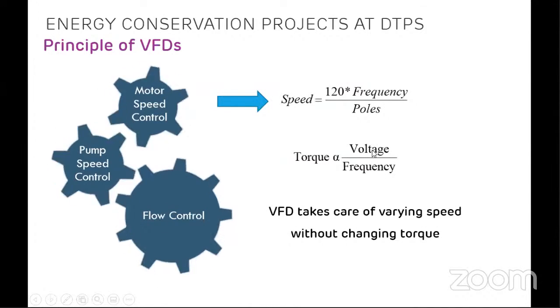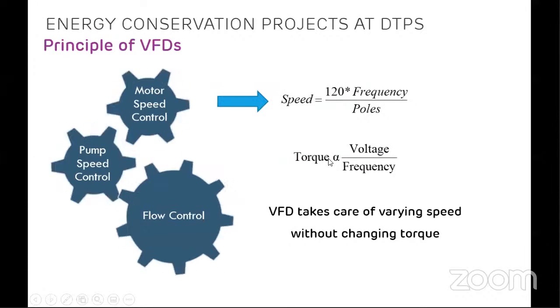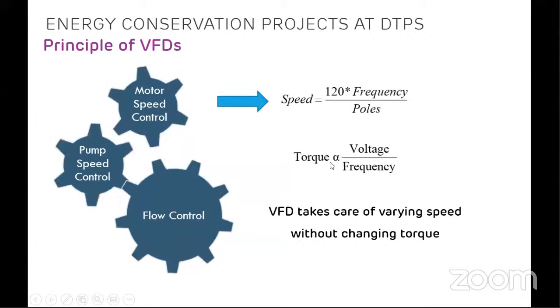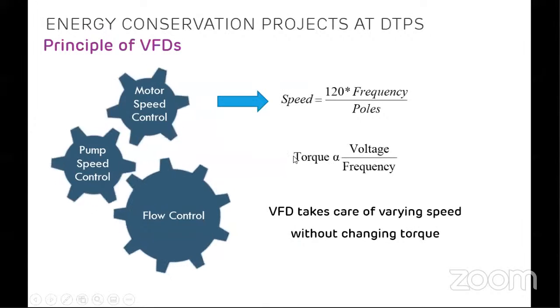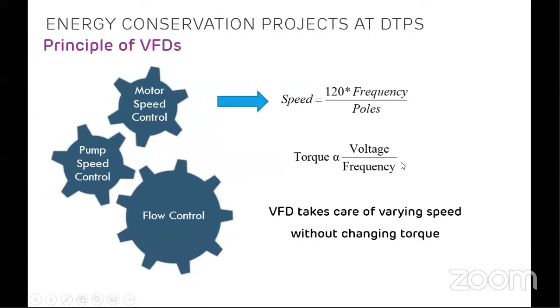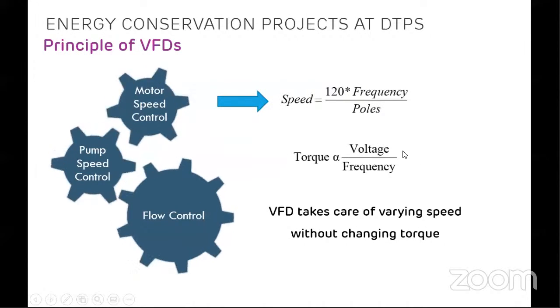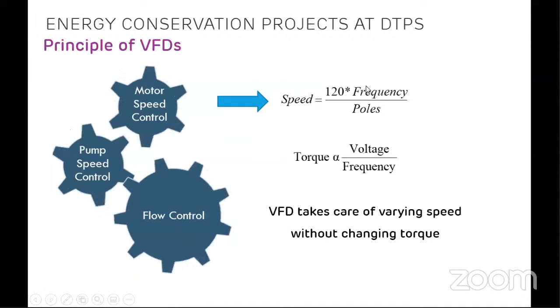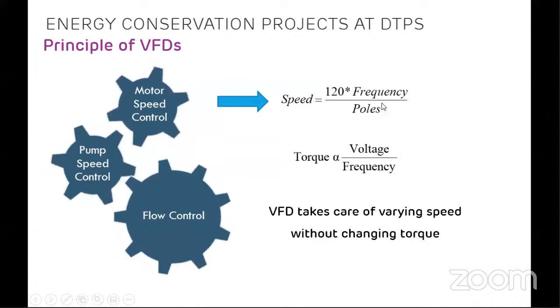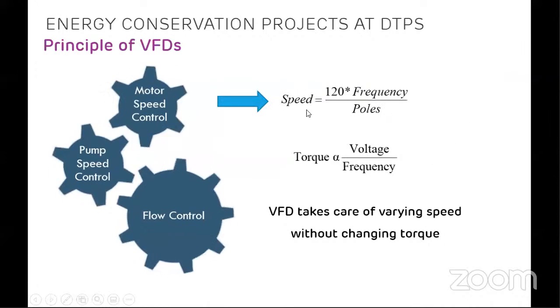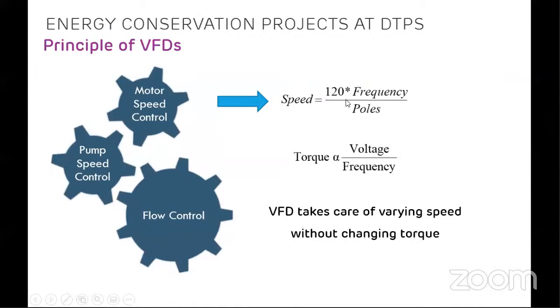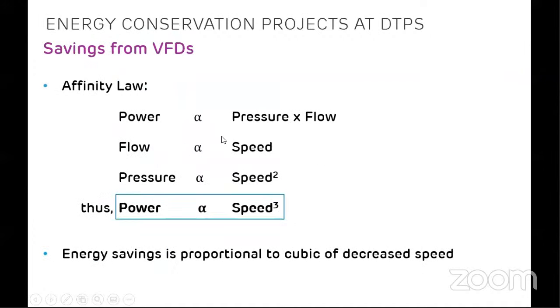torque of the motor is proportional to voltage upon frequency. Higher the voltage, more torque. Lower the frequency, more will be the torque. So a variable frequency drive increases or decreases the frequency to increase or decrease the speed. That is the basic simple feature of this. And when you increase or decrease the frequency as the speed varies, let us see how we gain power benefits or energy benefits from this.